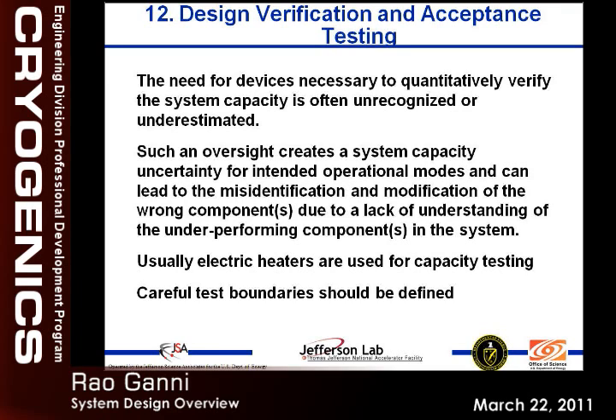So you want to keep enough margin, especially for thermal reliefs. At SNS we said it doesn't matter, we're going to make it very high class, high level, so they won't be anywhere close, because thermal reliefs don't need to be there. So when you select the components and rate them like that and leave yourself a bigger margin, we allowed for these things to drift with time and not cause you a helium leak. Did I answer? Yeah, okay.